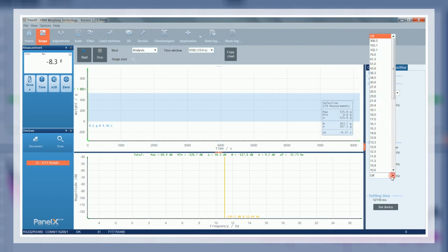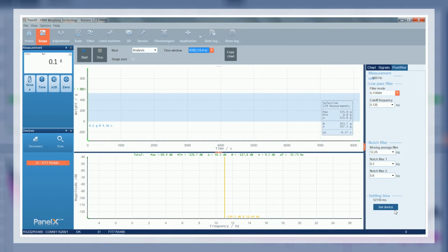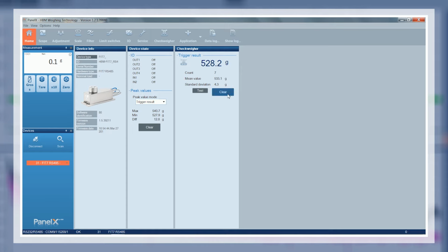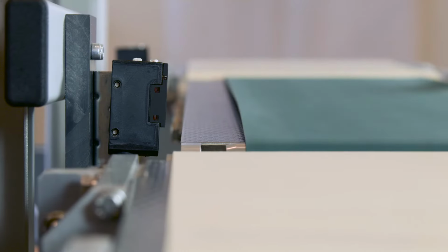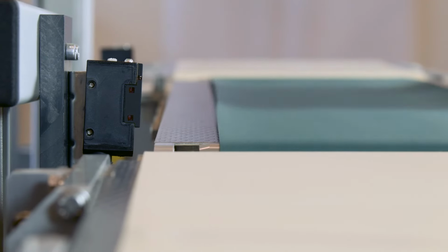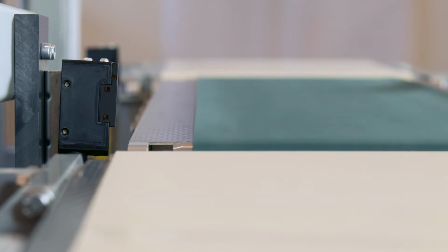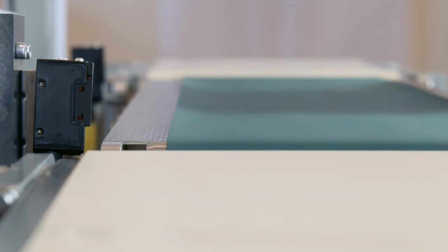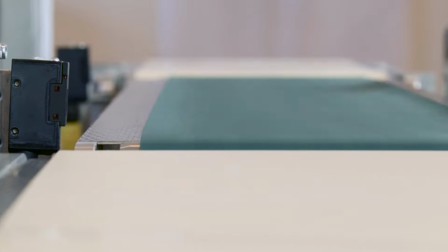Sources of noise and interference in the vicinity could be systems or machines whose mechanical vibrations are transferred onto the Checkweigher, or electromagnetic couplings via insufficiently shielded cables that cause scattering. Air currents could also result in the distortion of measured values. Once you save the data, you can access it again at any time via Panel X. That will allow you to implement constructive improvements and/or detect any errors when setting up the Checkweigher.